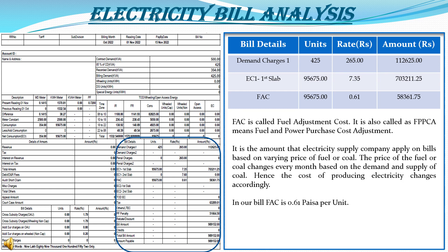Now the FAC section — Fuel Adjustment Cost, also called FPPCA: Fuel and Power Purchase Cost Adjustment. The electricity supply company applies this FAC in all bills because of the varying price of fuel or coal. The price of fuel or coal changes every month based on demand and supply, so the cost of producing electricity changes accordingly. In our bill, the FAC is 0.61 paise per unit. Multiplying 0.61 by 95,675 units, we get total FAC charges of 58,361.75 rupees.